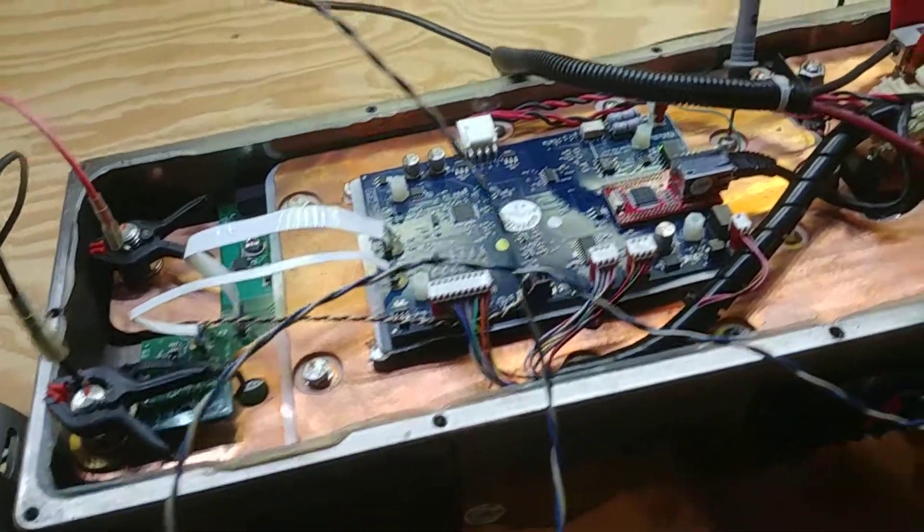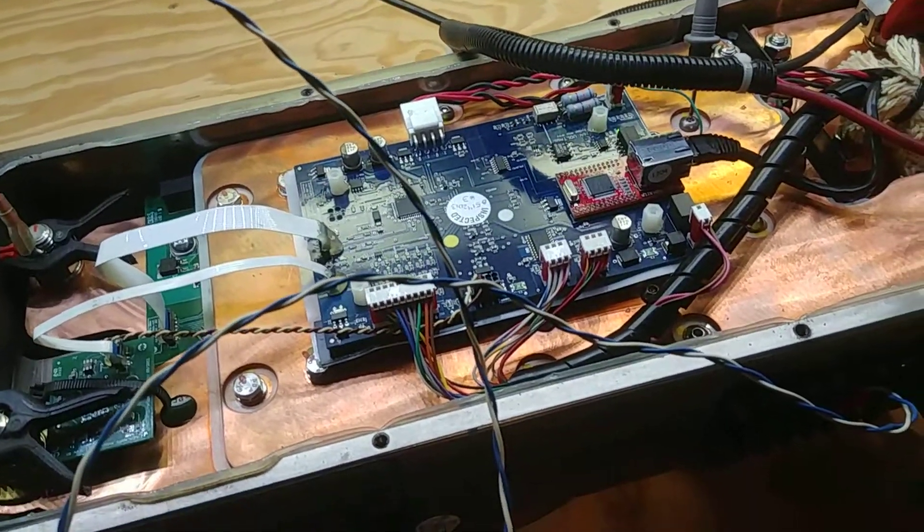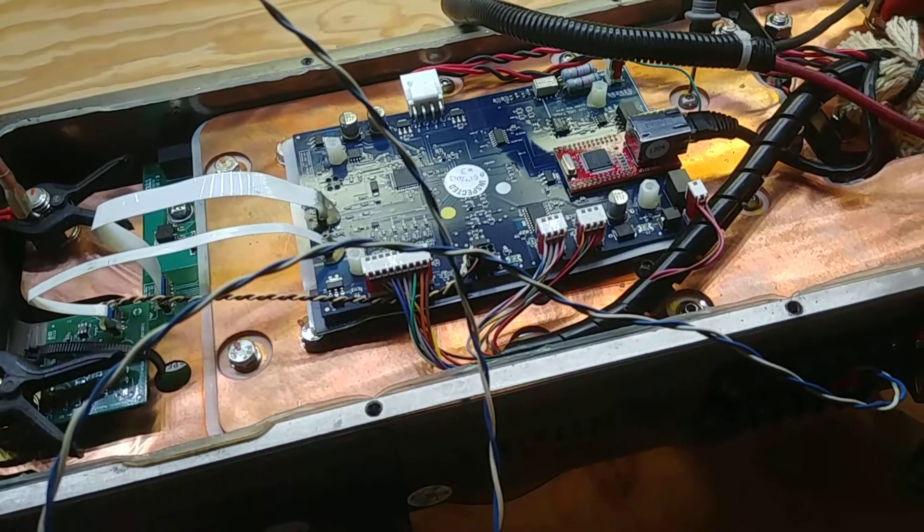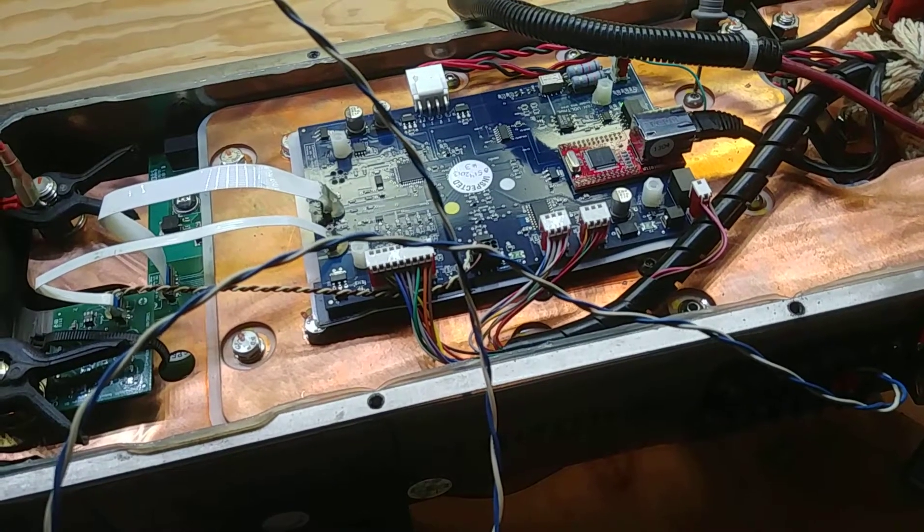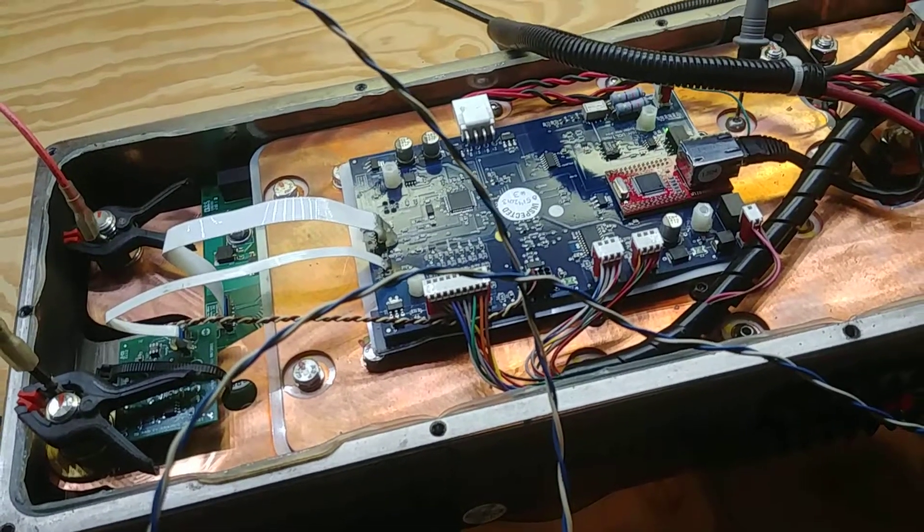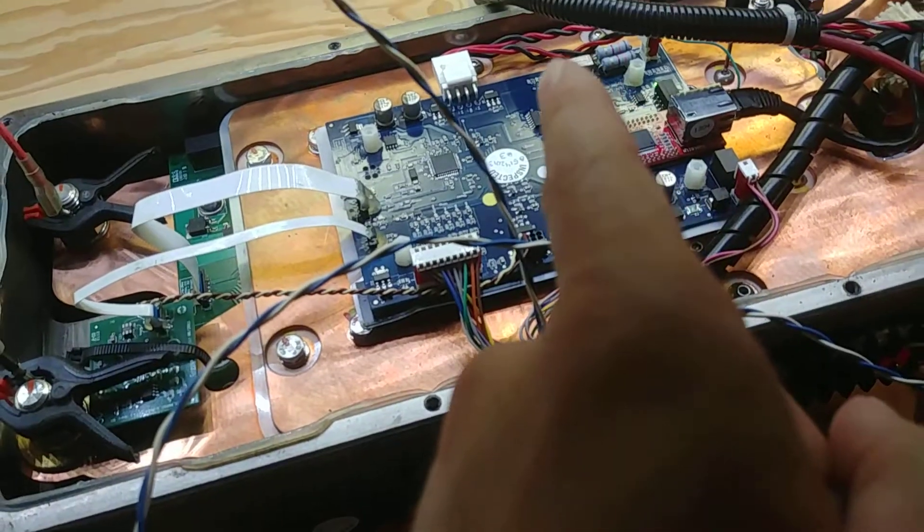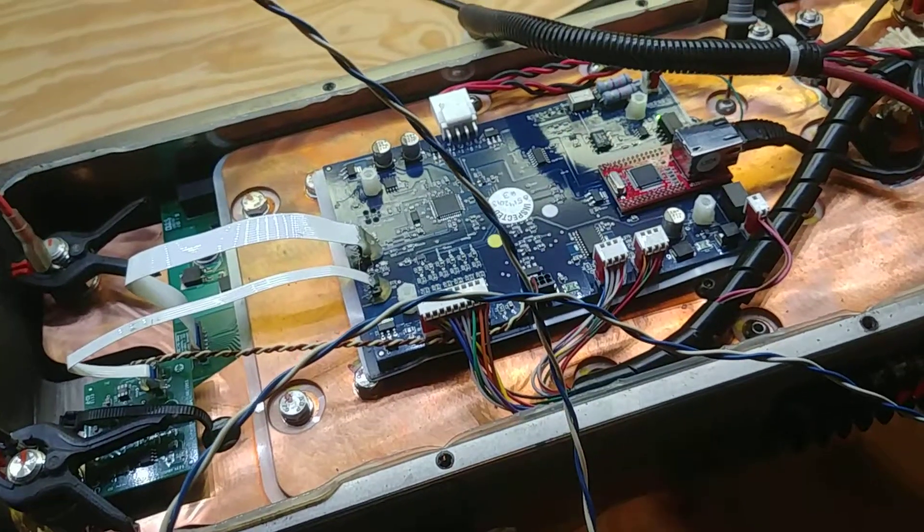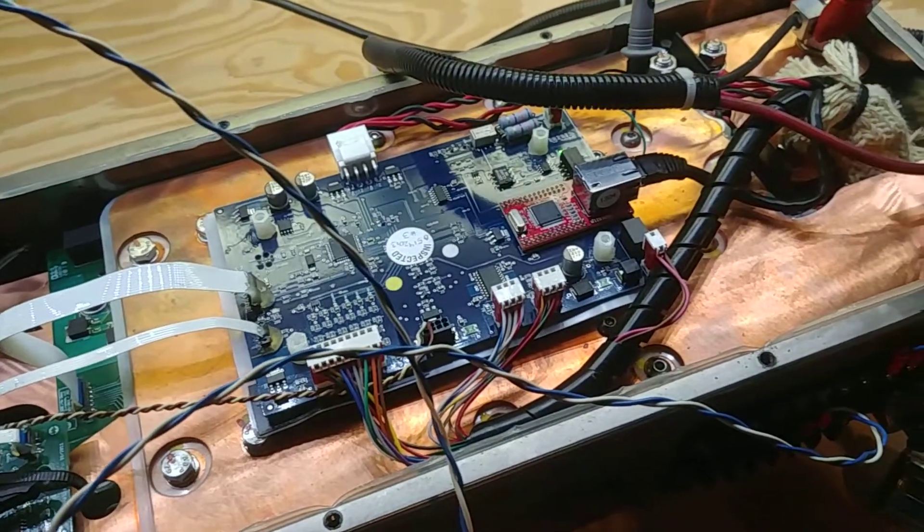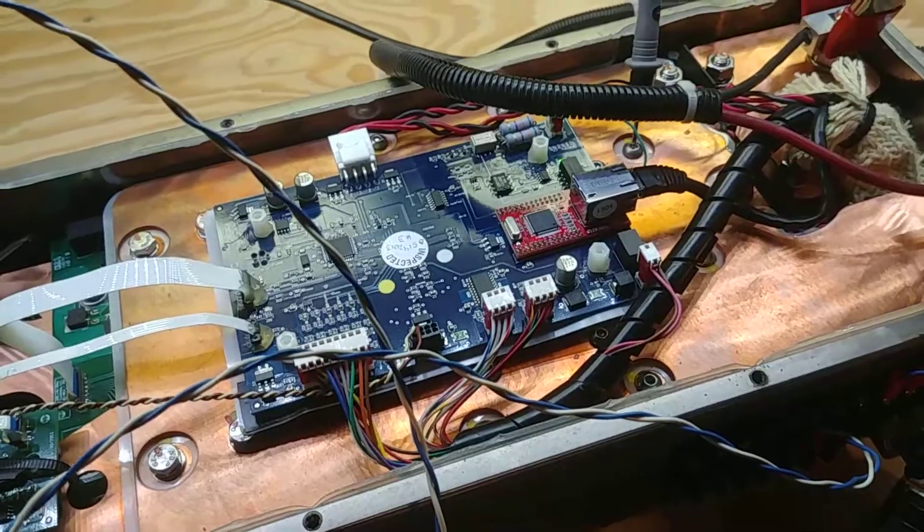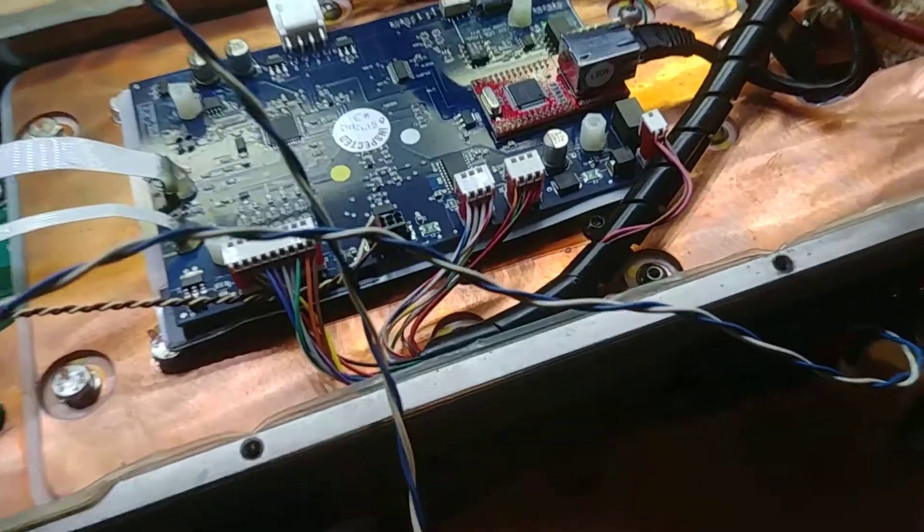So I don't know, I'm going to call it fixed. But I haven't really found a good, I mean, there's nothing shorted that would cause the pre-charger to pass enough current through the resistors to get it hot enough to melt them. I mean, it melted the circuit board and the insulator.